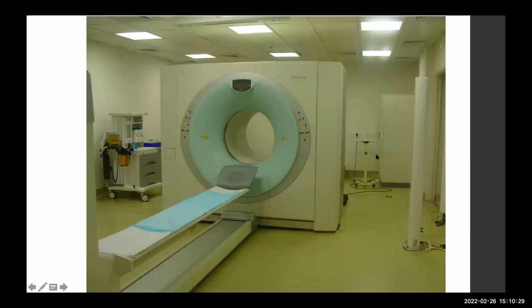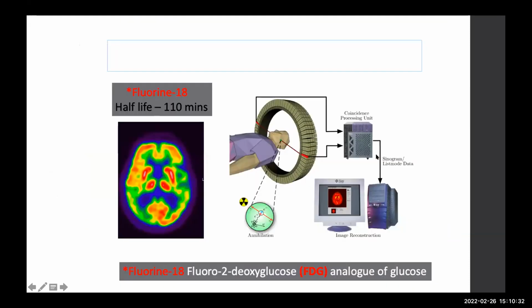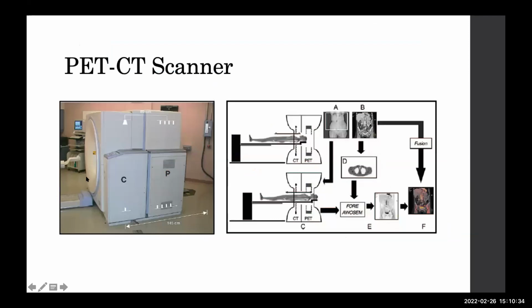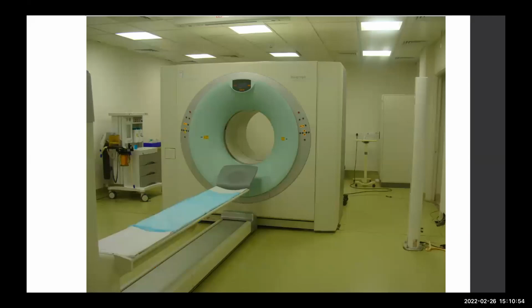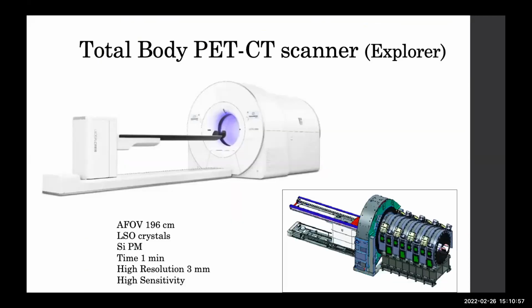In the current generation PET CT, the axial field of view varies from 30 to 60 centimeters. So you acquire the data in various bed positions. First you take the head, then the thorax, then the abdomen, then the pelvis, and then the mid thigh. So the data is acquired in 4, 5 or 6 bed positions, whereas in the single bed position of the total body Explorer, the whole patient is completed within 1 minute. So for those patients who are very sick and cannot lie for long, these cameras are useful.